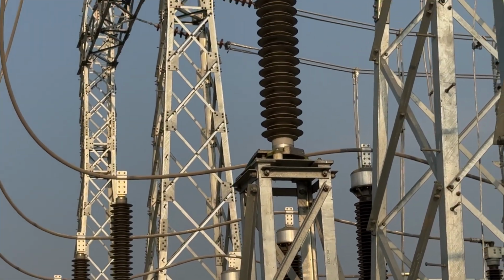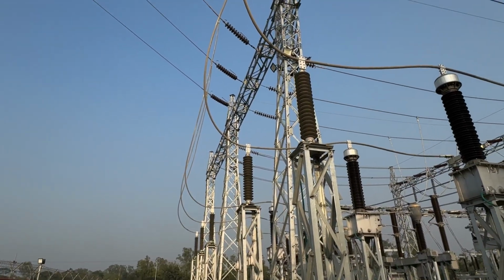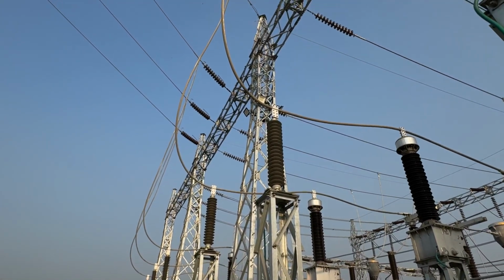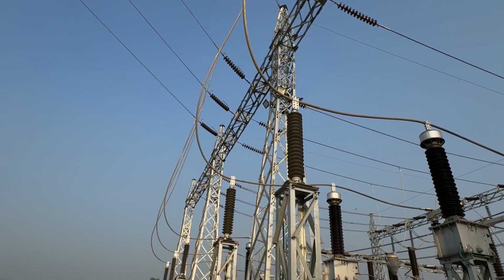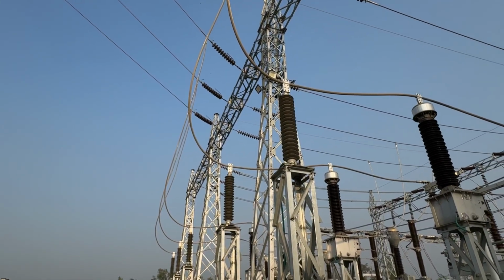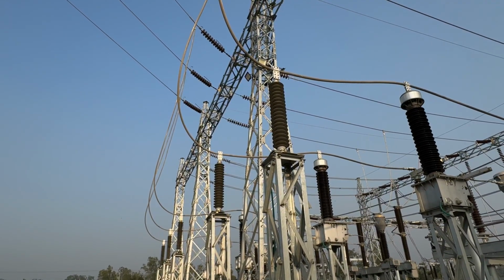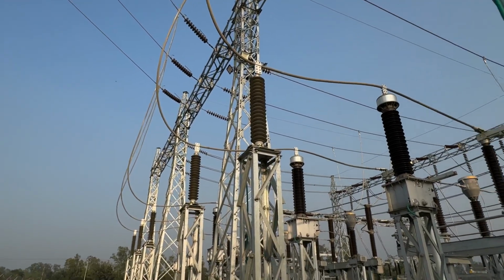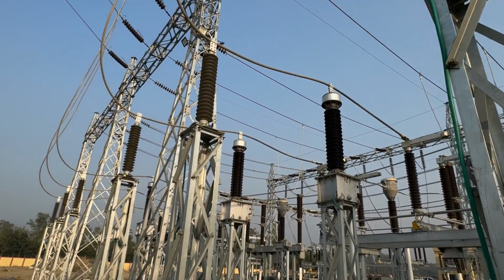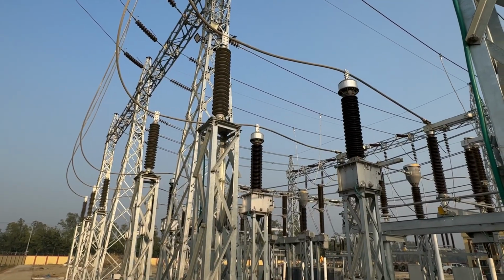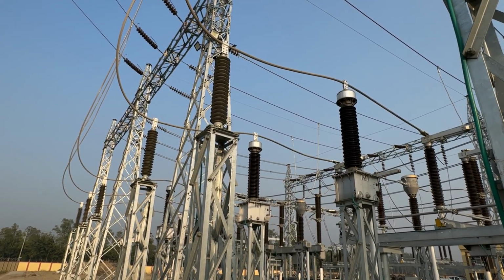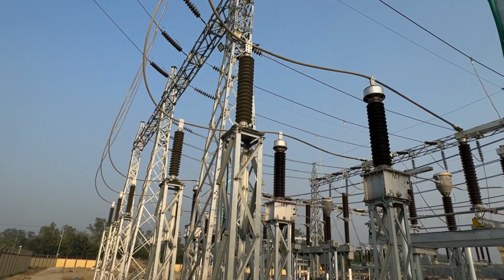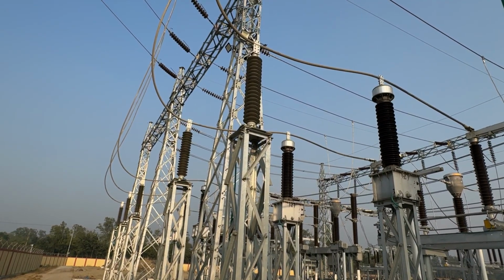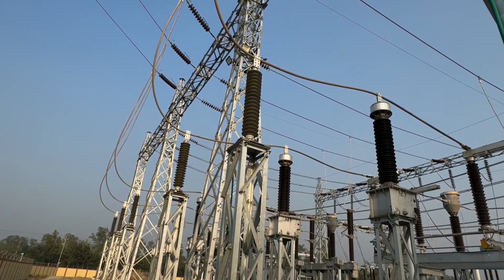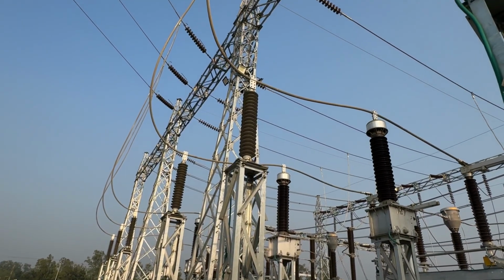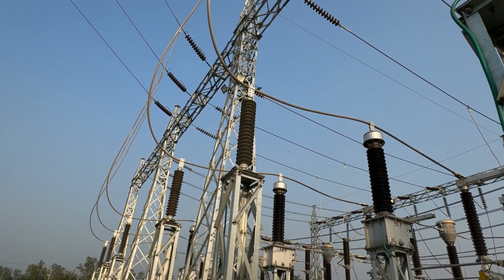If in any case this earth wire fails to arrest the lightning stroke, there are possibilities that the lightning strike enters the substation equipment and could damage the equipment. The function of the lightning arrestor is to arrest any type of lightning strike in the conductors if there is one.